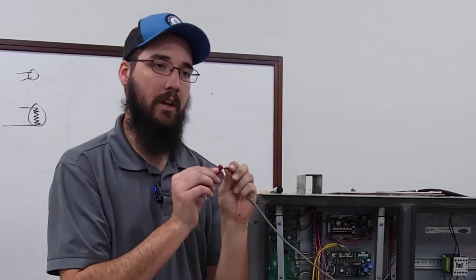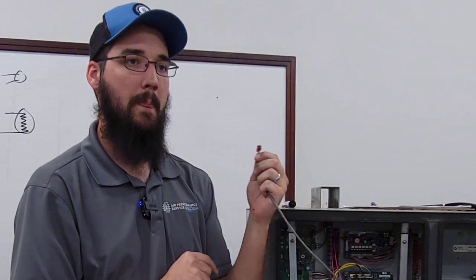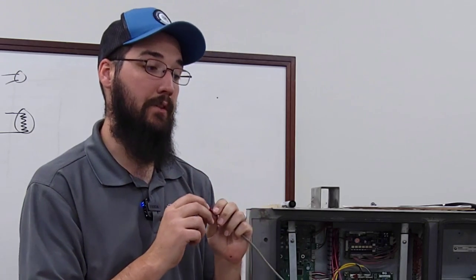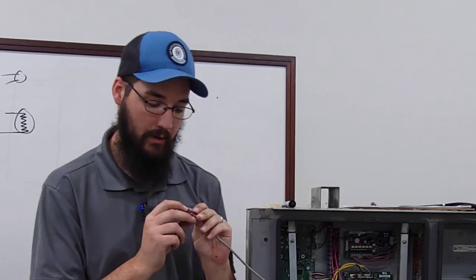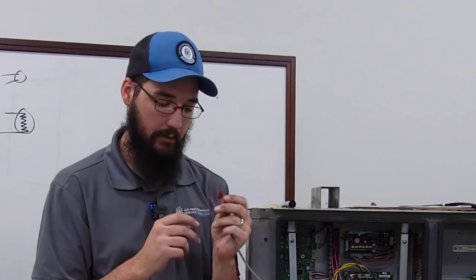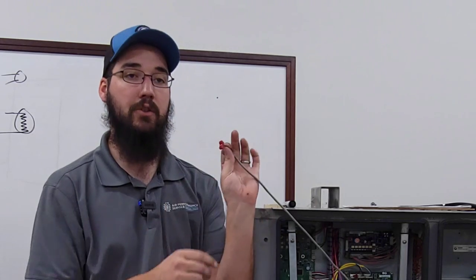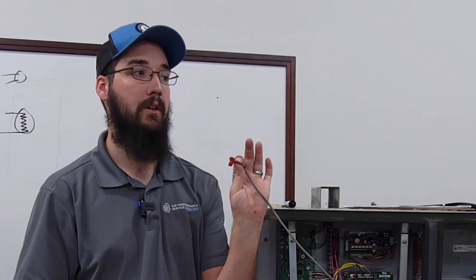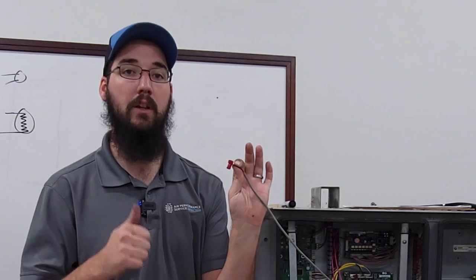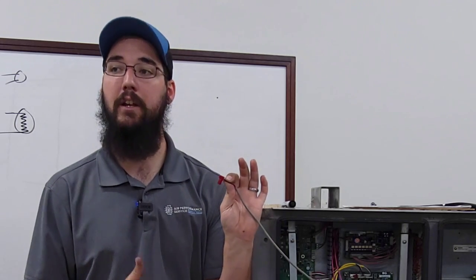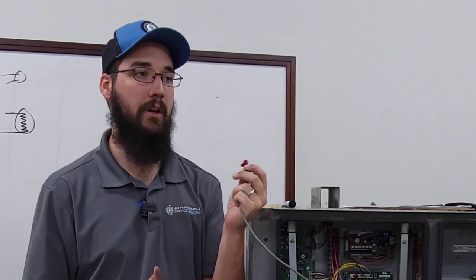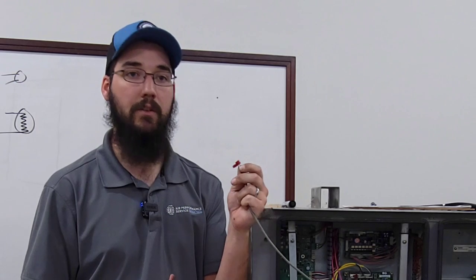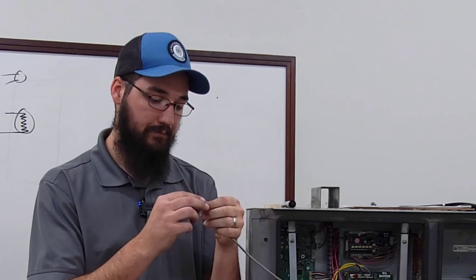For thermistors on this particular board, this is a pretty common thermistor-type plug. I'll tell you something the factory did that I caught the other day. You've got to make sure you unplug this — don't test this with it on the board, because that board will affect your reading and you will not get an accurate result.